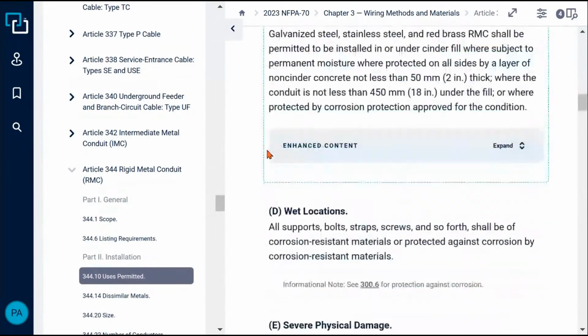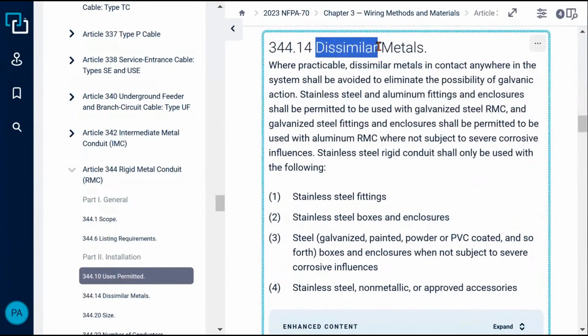I don't see anything in here - this is just talking about corrosive environments under wet locations, physical, dissimilar metals. Now we see the words fittings, cabinets, boxes, steel, everything. Okay, wait a minute, let's look in here and see real quick. It says, let's see here: where practicable, dissimilar metals in contact anywhere in the system shall be avoided to eliminate the possibility of galvanic action. Makes sense. Stainless steel and, here's what we want, aluminum fittings and enclosures shall be permitted to be used with galvanized steel RMC, and galvanized steel fittings and enclosures shall be permitted to be used with aluminum RMC.